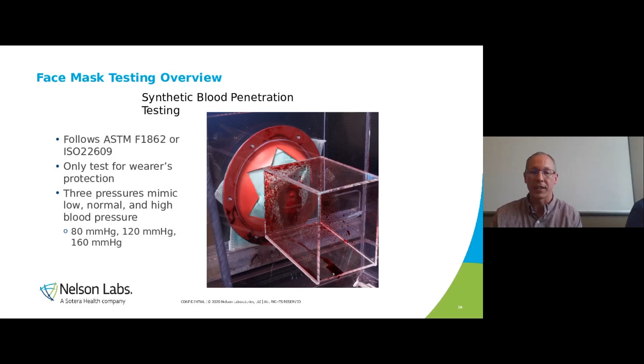So that's what we're testing, the different pressures. We have options for a low or normal or a high blood pressure. In the US, there are 3 options, level 1, 2, and 3, based on those pressures. In Europe, they only require the middle 120 millimeters of mercury pressure. And they only have 1 mask that complies with protection for synthetic blood. It's their type 2R mask.